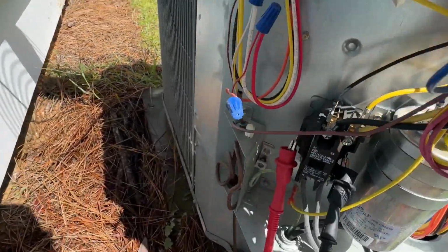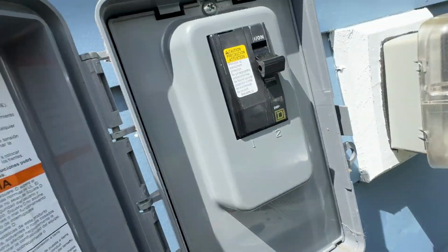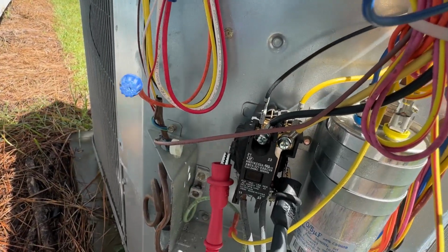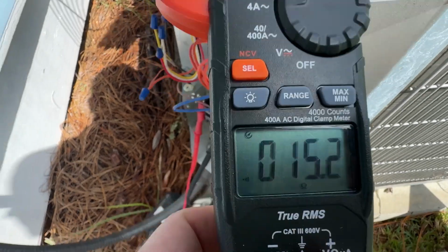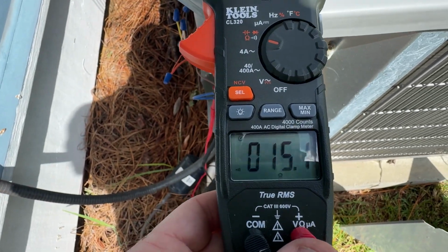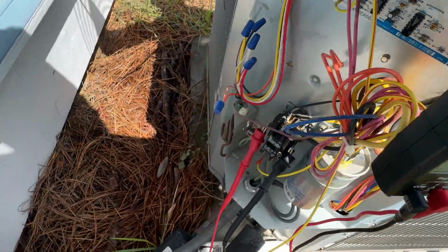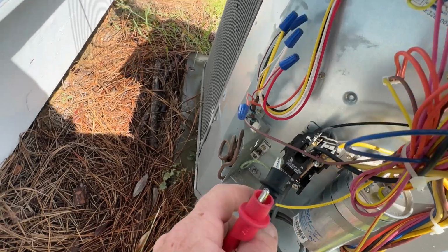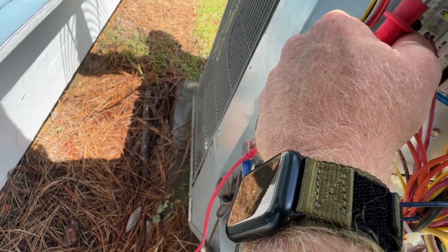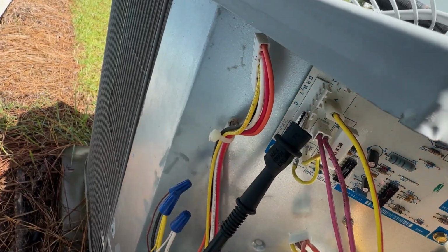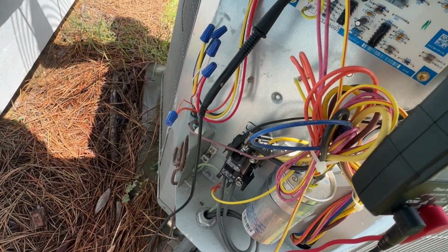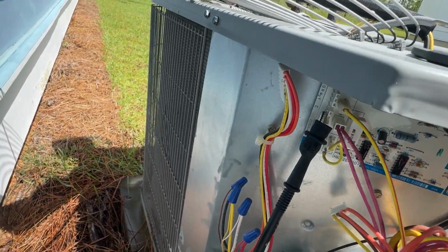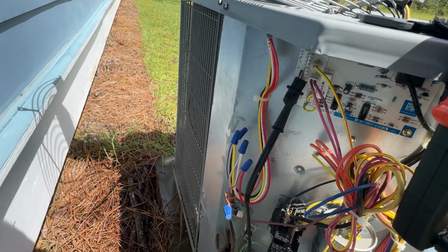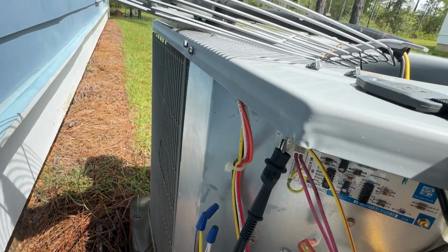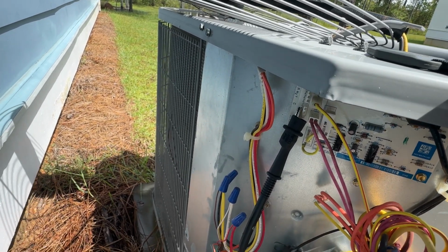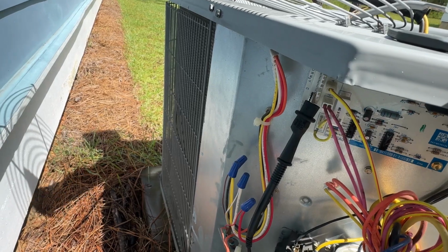So I'm testing out the contactor coil. Please make sure you turn the power off before you start pulling wires. But I'm testing the contactor coil, and we're at 15, which is good. You want between 10 and 20, so that's good. So now I'm just gonna check each one of these little prongs on the board and test it to ground and see what we're getting. I'm not getting any hits, so it might actually be going to the thermostat or something. We'll double check everything once we get done.